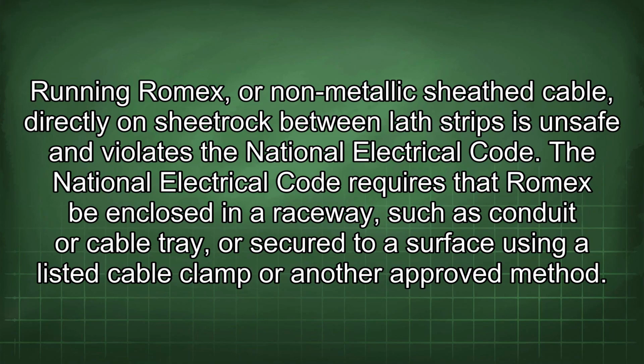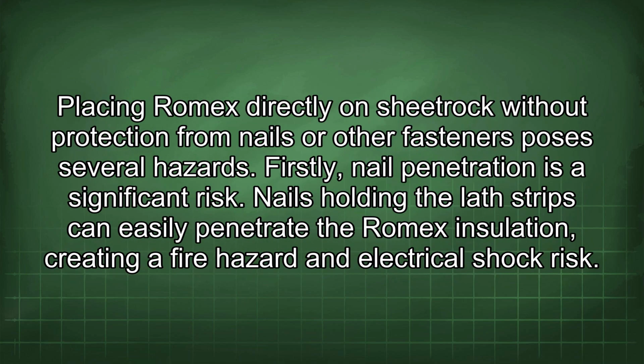Running Romex or non-metallic sheath cable directly on sheetrock between lath strips is unsafe and violates the National Electrical Code. The National Electrical Code requires that Romex be enclosed in a raceway, such as conduit or cable tray, or secured to a surface using a listed cable clamp or another approved method. Placing Romex directly on sheetrock without protection from nails or other fasteners poses several hazards.